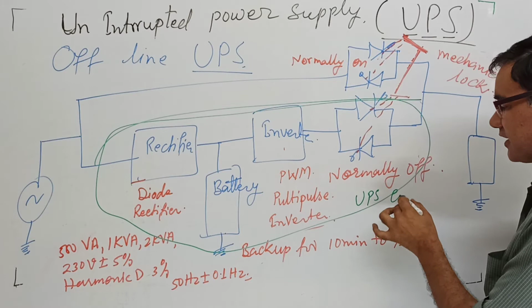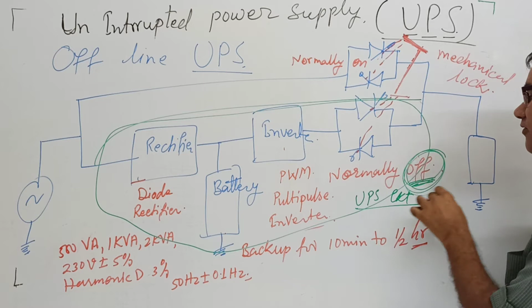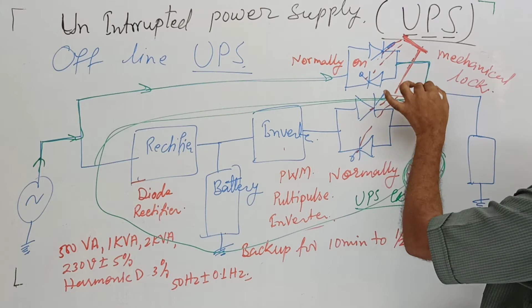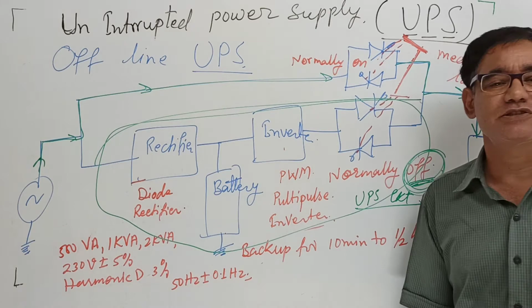You know what happens in this offline UPS? This is the main circuit and this is the UPS circuit. The UPS circuit is normally off, and power from the main source is directly fed through this controlling switch or regulator to the load. The main switch is normally on, and that's why its name is offline UPS. The main power directly goes to the load. There is no voltage regulation, no controlling, no backup. A very small backup, a small circuit, less harmonic control, less filter requirement. It's a simple, low cost arrangement.